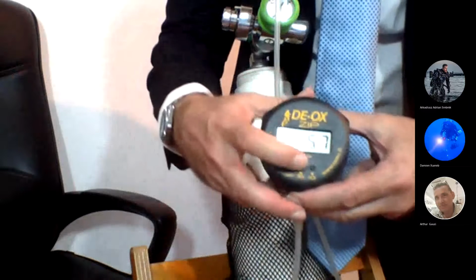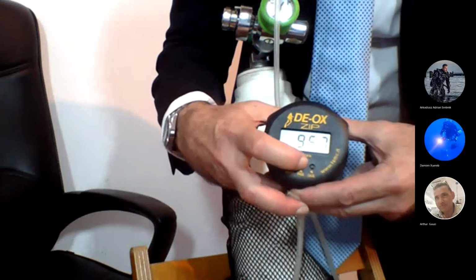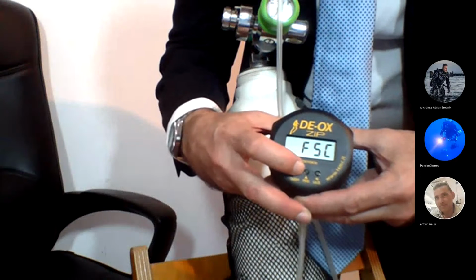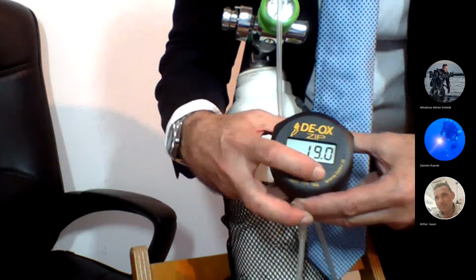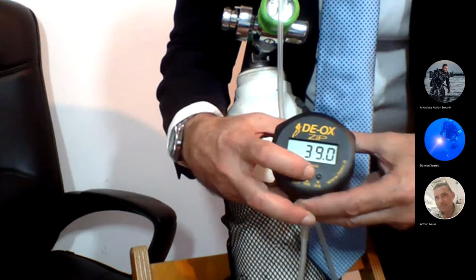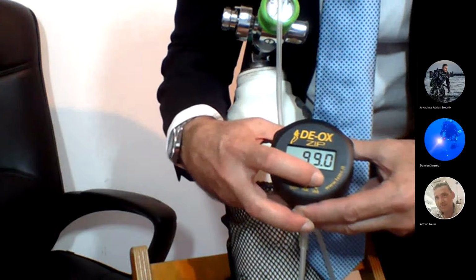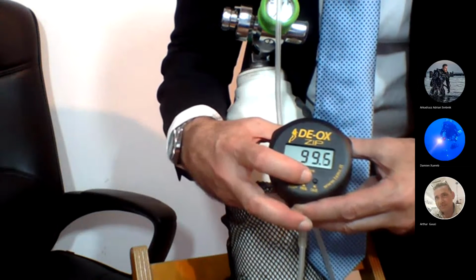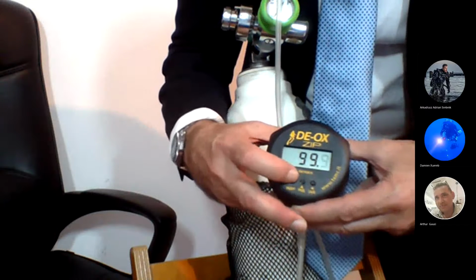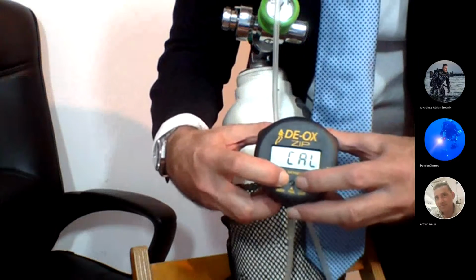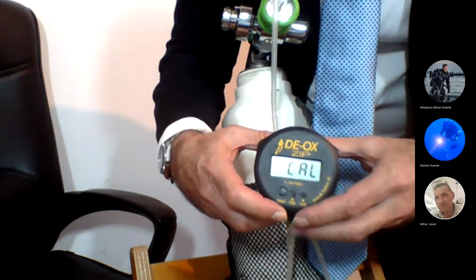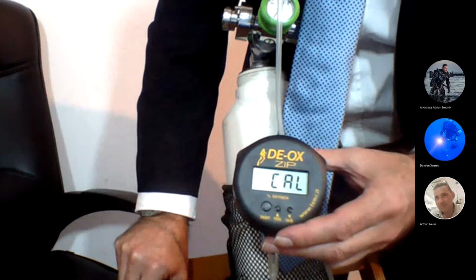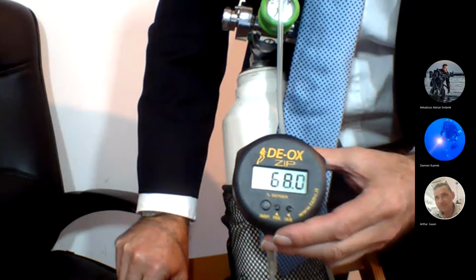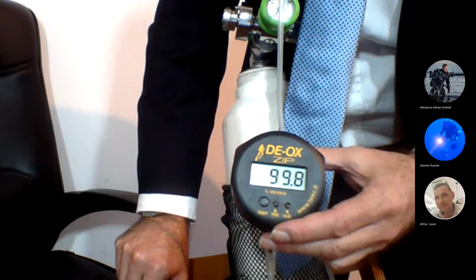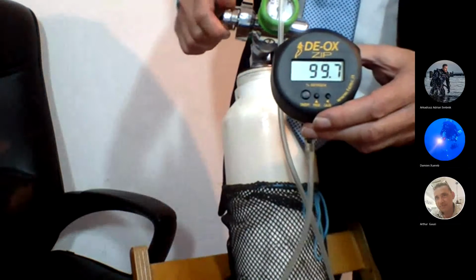Now I can do better. I can go to the calibration. I can set it to 99%. That is pure oxygen, okay? Then I'm flowing pure oxygen and I can say, hey analyzer, I'm in 100% oxygen, I'm doing the calibration now. Okay, now I can turn the valve off.